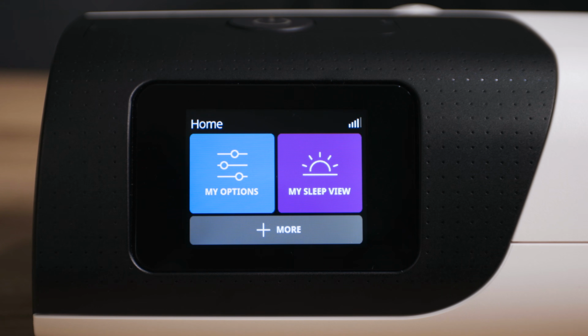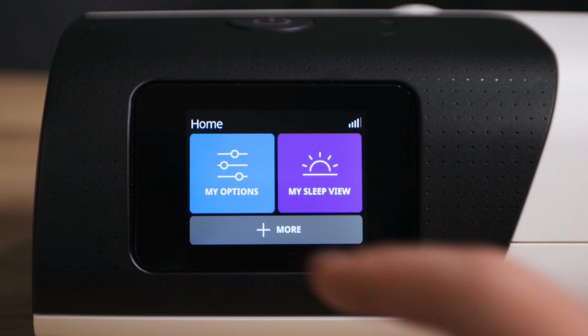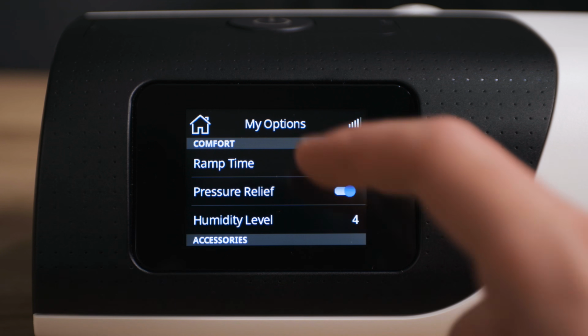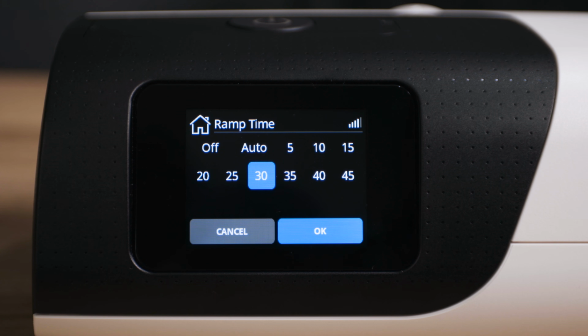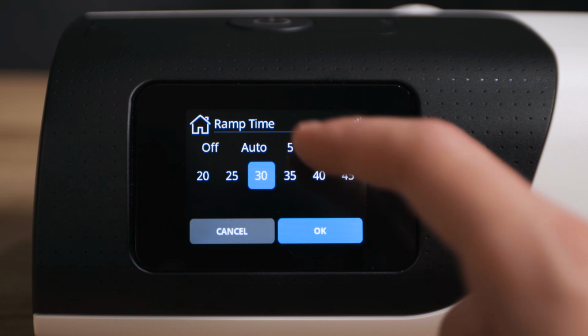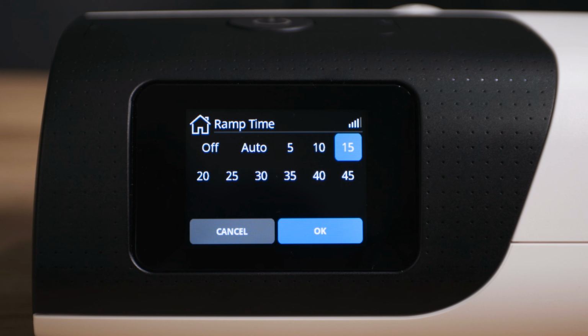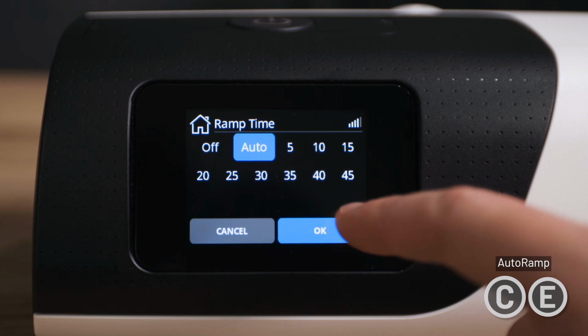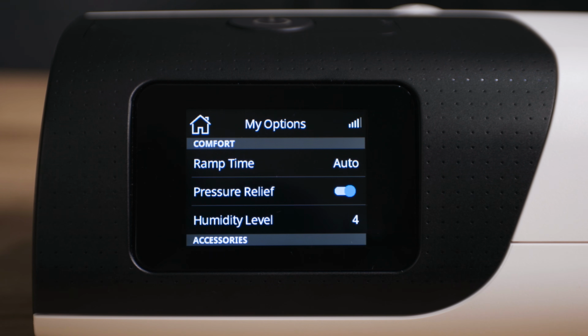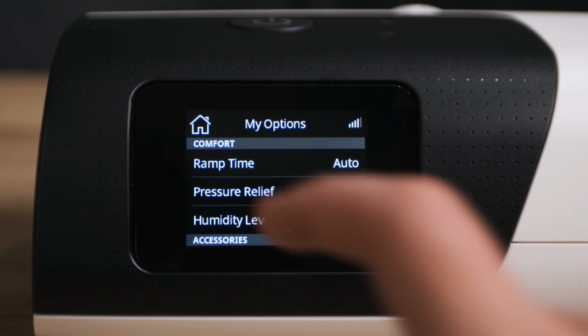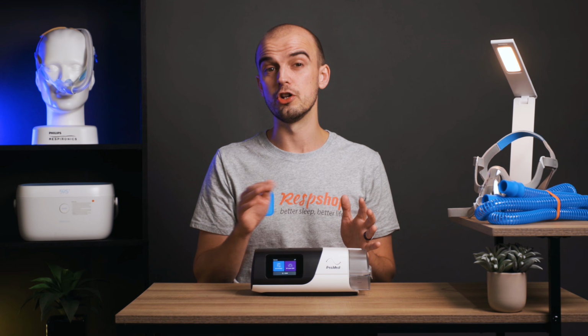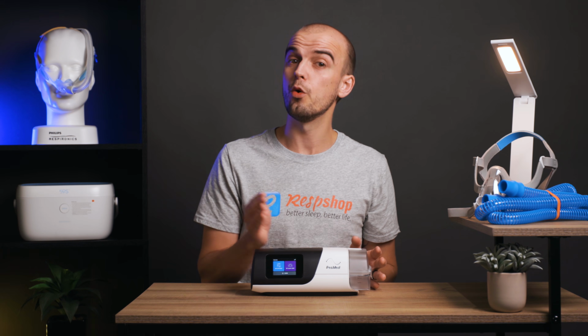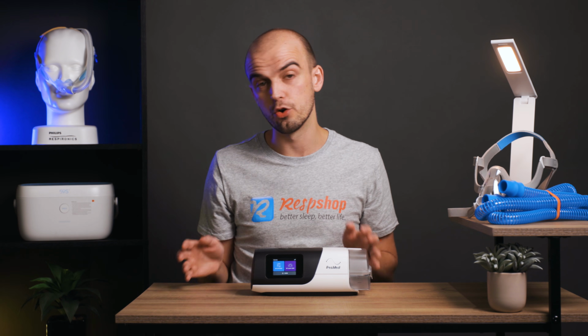But the bulk of the information and customization is found in the My Options menu, the first of which is ramp time. Here you can adjust the period of time that it takes for the pressure to slowly ramp up to the final prescribed amount in 5-minute increments. Now traditionally, this ramping time begins from the onset of therapy, but ResMed has an auto ramp feature. This allows the AirSense 11 to detect when the user has actually fallen asleep, and only then does it begin to ramp up the pressure to the prescribed amount. This way, whether it takes you 5 or 50 minutes to drift off, the unit will deliver the low starting pressure for maximum comfort the whole time.